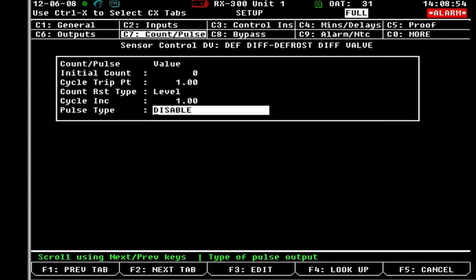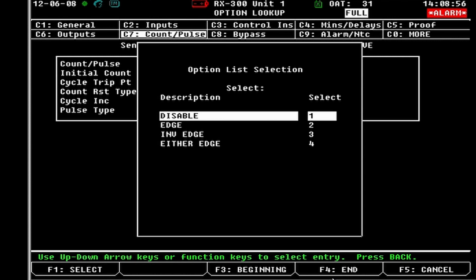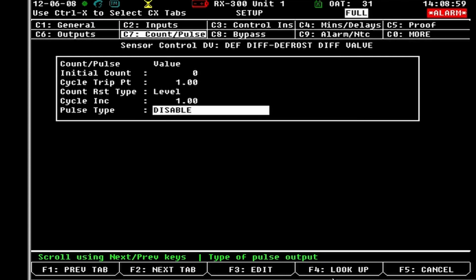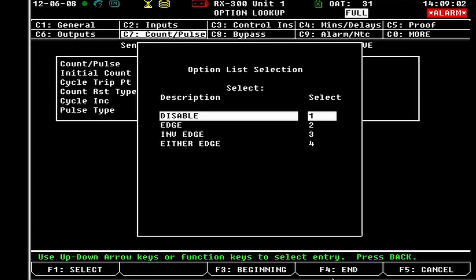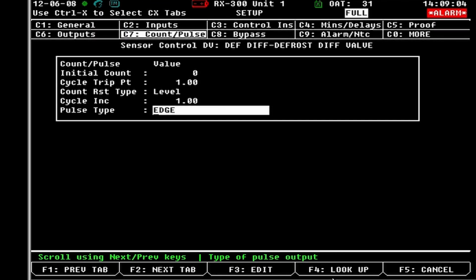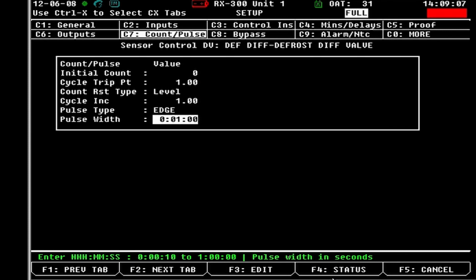So if we hit lookup and we go edge, and this is the pulse width. So it'll pulse it on for a minute and then off when it switches back, then on for a minute. So this would be useful if you're trying to do some like liquid injection, oil pulsing. So if you wanted to pulse an oil solenoid every time a level switch made and you wanted to drain a reservoir into another tank, you could do that.